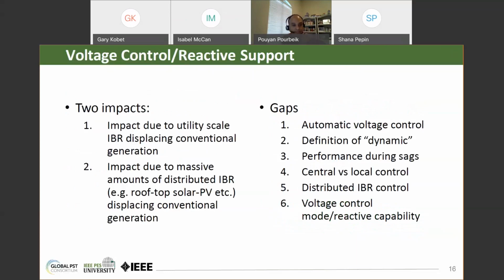So two of the most important gaps in terms of voltage control was that, and I'll show you examples here of some recent tests of actual plants. Renewable generation, inverter-based generation can definitely do voltage control, can do it very well, very fast. The gap at the time of this report was that some of these definitions I put here on the right-hand side: automatic voltage control, what do we mean by dynamic? What is the performance expected for a SAG? What's central versus local control? What about distributed IBR?